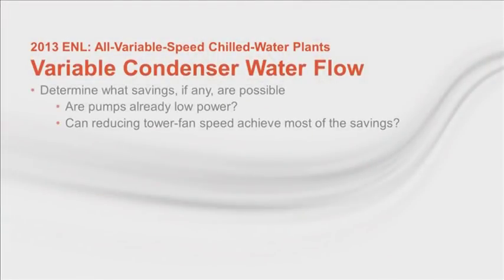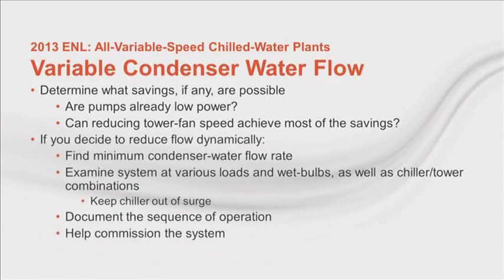As we discussed in the 2011 and 2013 programs, you need to determine whether or not dynamically changing the condenser water flow rate should even be considered. If you've already minimized the condenser water pump kW, for example by reducing design flow rate to 1.5 or 2 GPM per ton, it may not even make sense to take the time to look further. The pumps already have a really low contribution to the chiller plant energy picture. If you already have VFDs on your cooling tower, reducing the tower fan speed dynamically can achieve a lot of the potential savings, and it's simpler.